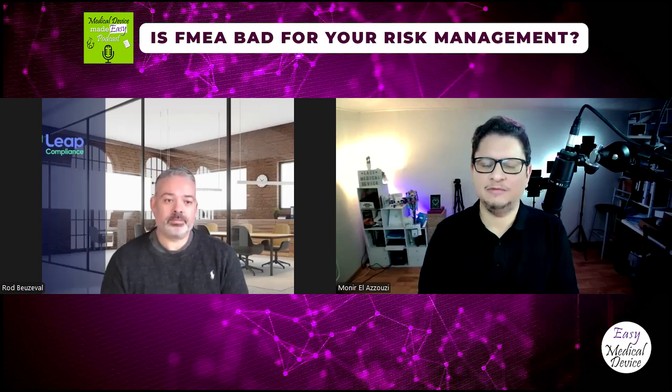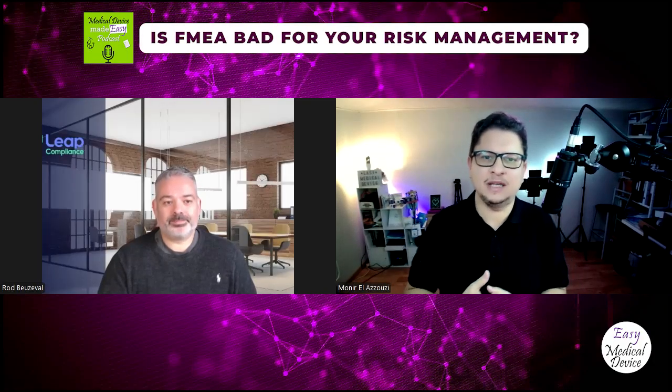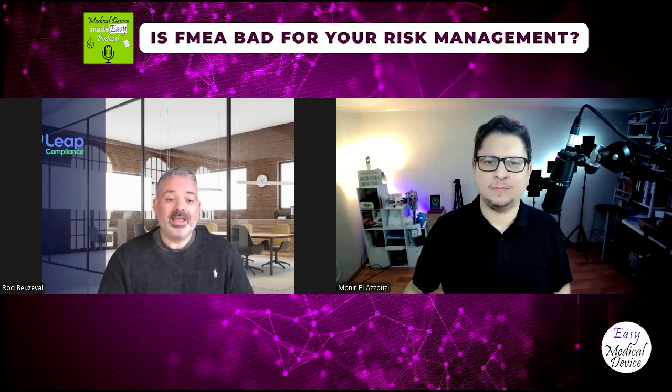The standard itself, because we also have this misunderstanding when you look at the ISO 14971, it's not obliging you to use any methodology. It's just telling you that you should do an analysis, you should do a collection of information or identification of harm, of all those hazards, etc. Find mitigation, etc. But it's not giving you any methodology. Even if in the annex they are giving you some kind of information, it's information only. So this is really where sometimes the mistakes arrive when people say, "Oh, you should use FMEA." Correct. Exactly that. And FMEA is a very convenient tool.